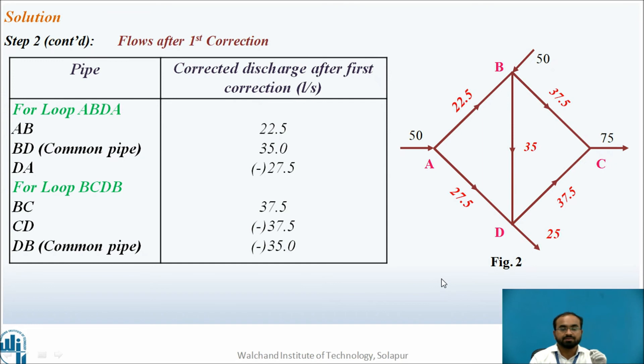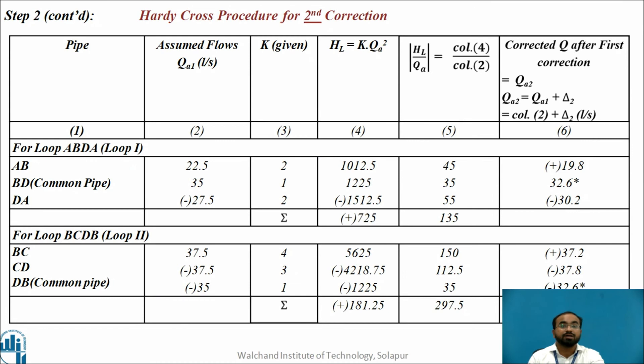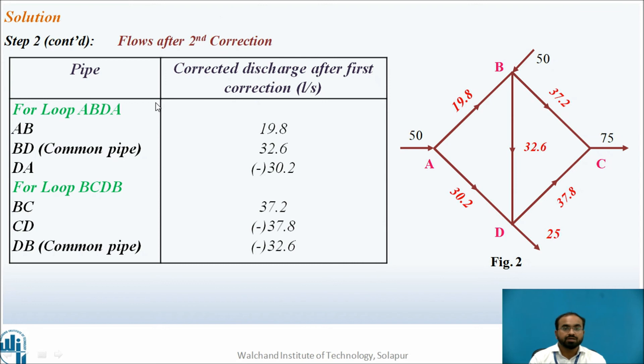The same procedure is done for the second iteration, but in column 2 I use the corrected flow rates from iteration 1, not the assumed flow rates. After iteration 2, the corrected flow rates are: AB equals 19.8, BD equals 32.6, DA equals minus 30.2, BC equals 37.2, CD equals minus 37.8, and DB equals minus 32.6.